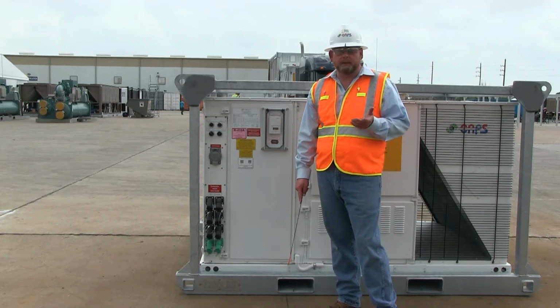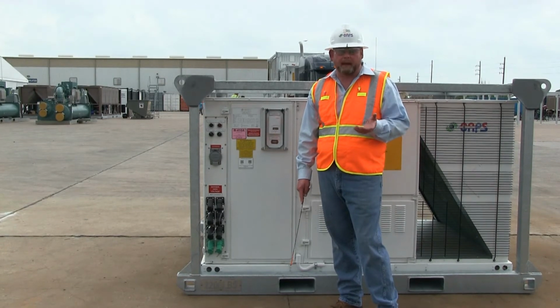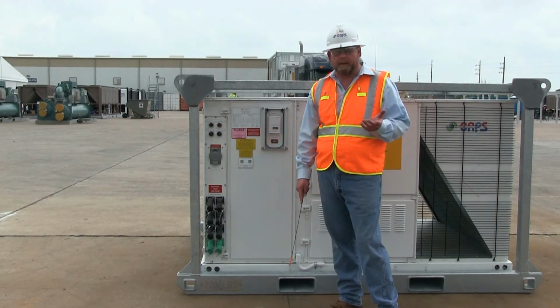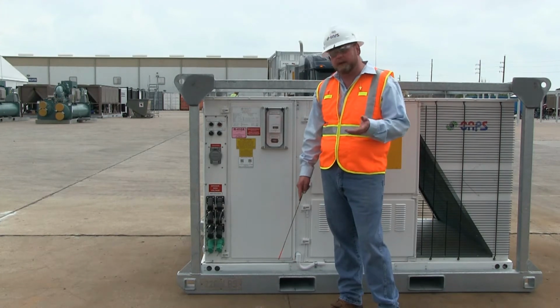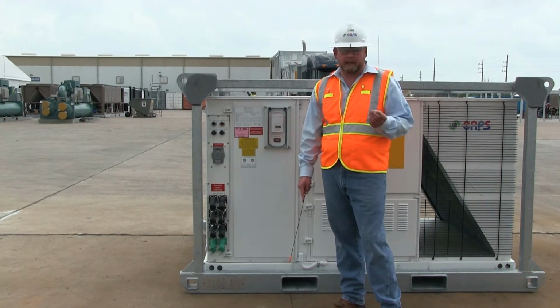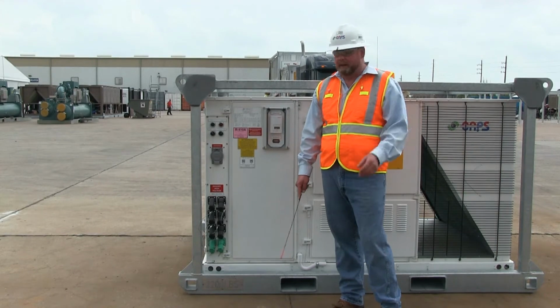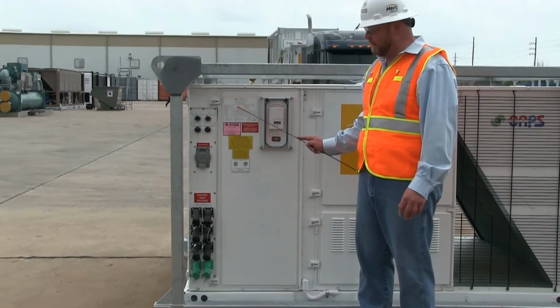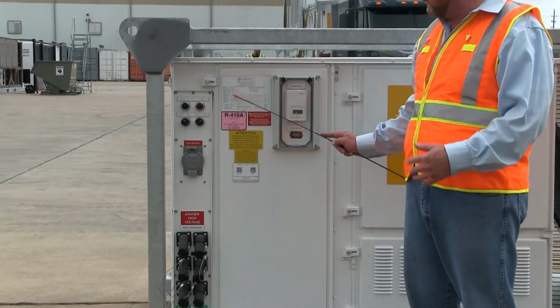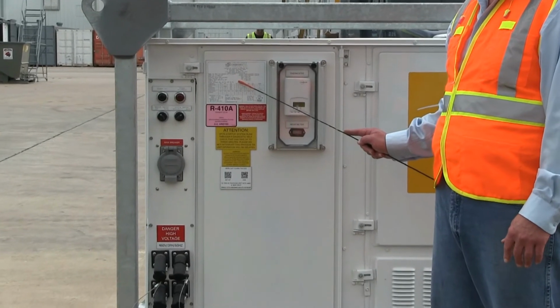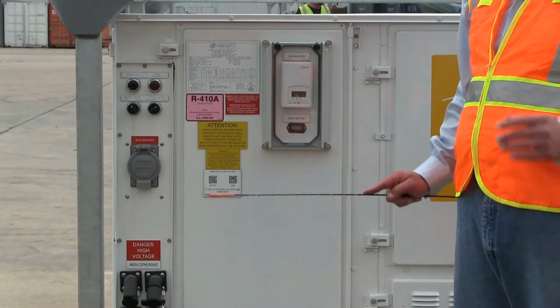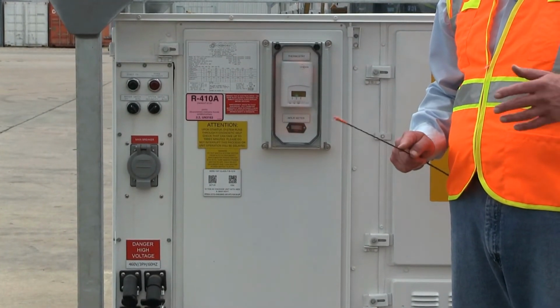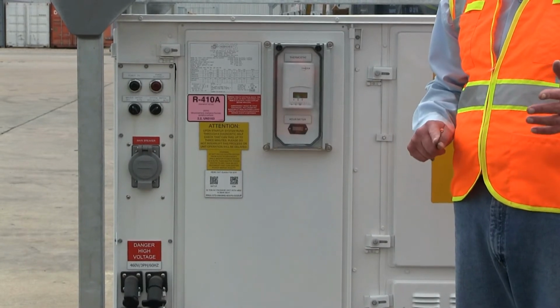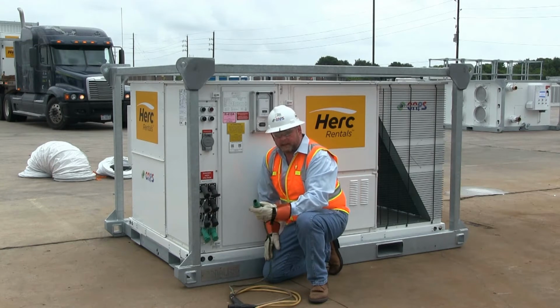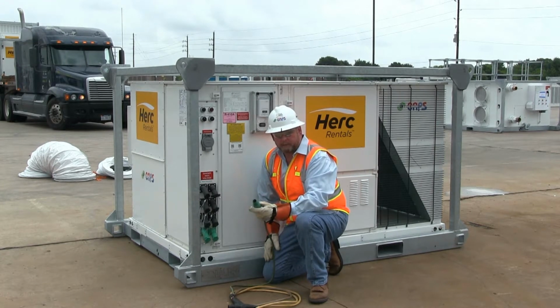Now that we have the unit set in place, we want to determine the power requirements for a specific application. The 10-ton unit is capable of doing cooling, heating, and dehumidification. If you'll reference the data tag here, each of those values is clearly marked on the CAPS data tag. You'll need to make sure that your house power supply source or your generator is properly sized for that particular application.